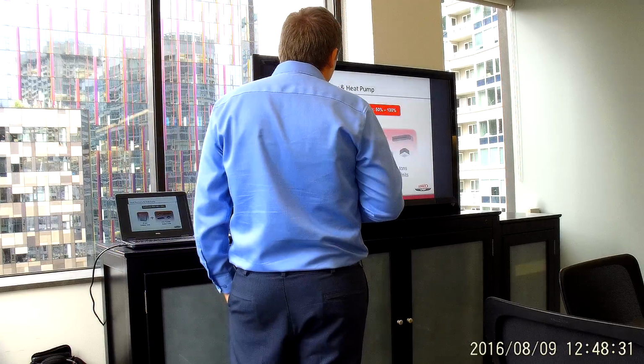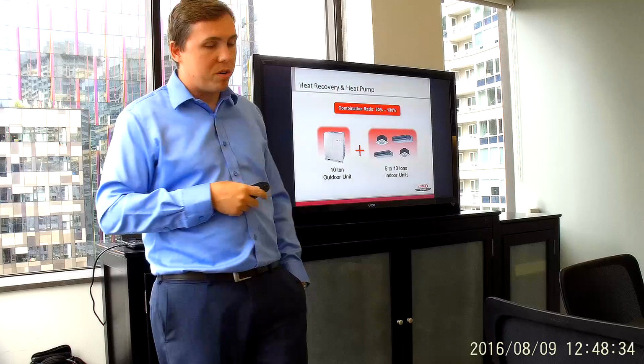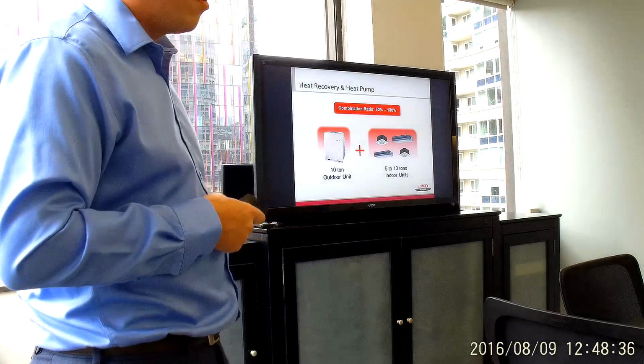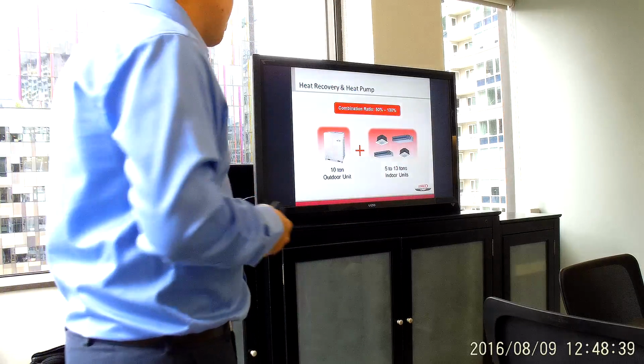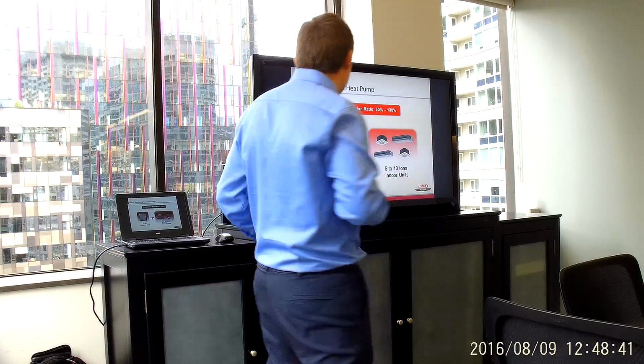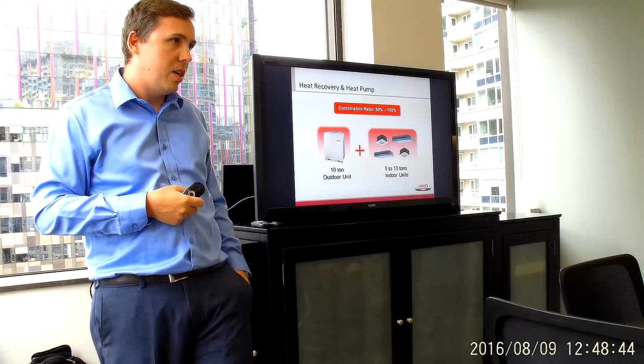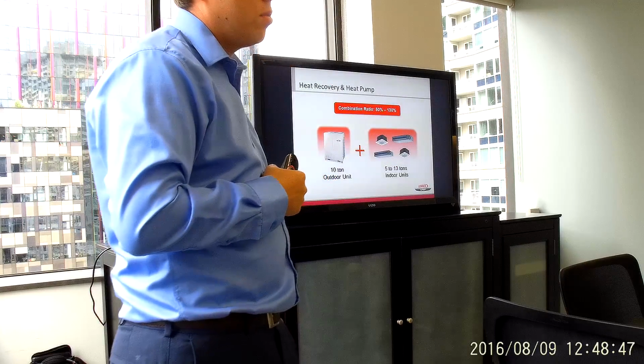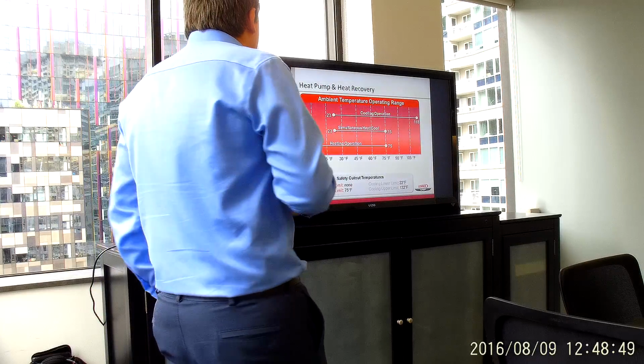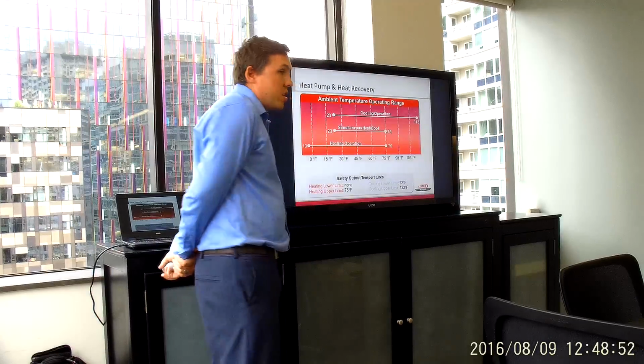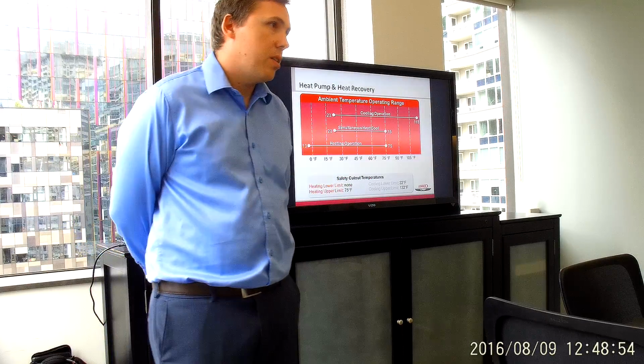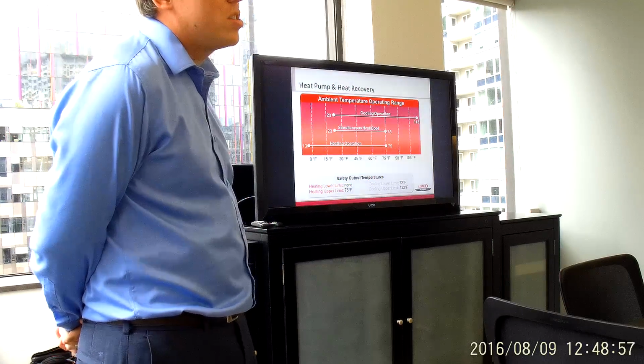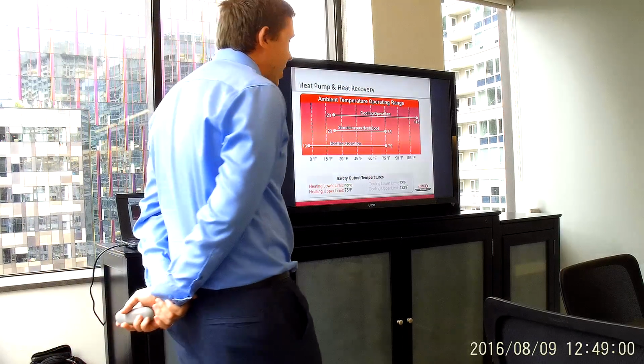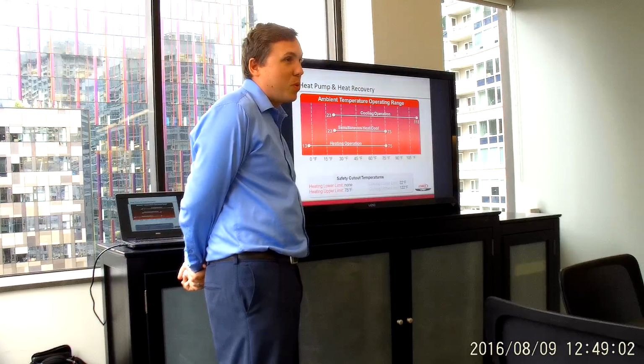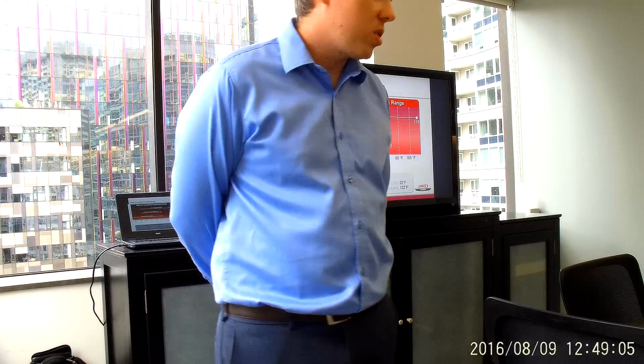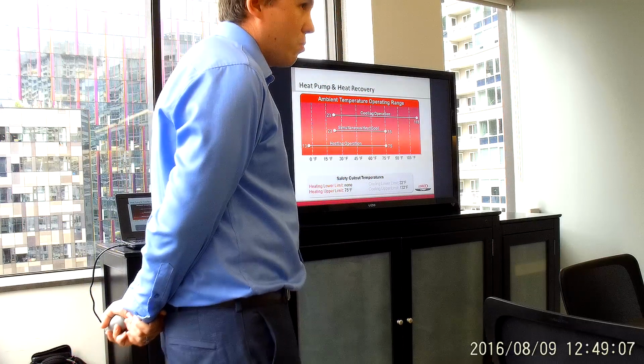Okay. Combination ratio, 50 to 130%. We've talked about diversity, talked about connecting these systems together, so you can do multiple indoor units versus this one outdoor unit, up to 13 tons versus a 10 ton, or as low as 5 tons for that 10 ton unit. All right. Our temperature range, our heating operation goes down to minus 13 degrees Fahrenheit. So, we're never going to see that up here. Well, unless you're talking about Snoqualmie, but for the most part, here in Seattle, up in Vancouver, in Portland, you're not really going to have any worries with regards to temperature ranges here.